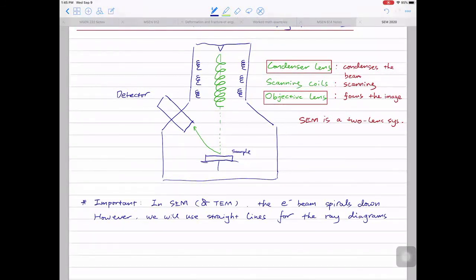The beam spiraling down won't really affect what you see in SEM. But in TEM — if you take the TEM class in the spring — there's one artifact from TEM imaging: when you increase the magnification, the image on the camera actually rotates. This is called magnetic rotation, and it's the result of the electron beam spiraling. When you zoom in and increase magnification, the image actually rotates because the beam spirals down.